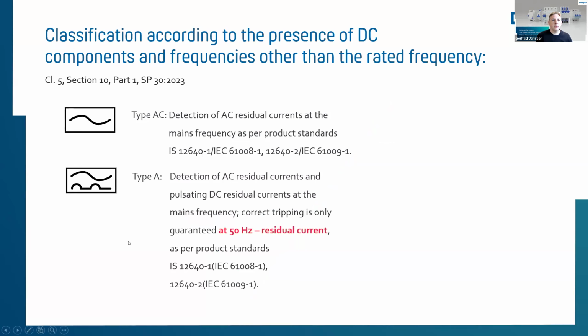When we come to the history of RCDs, everything corresponds to the presence of DC components in the different systems. So the classification is according to the presence of DC components and frequencies other than the rated frequency. We are starting with an RCD type AC, which is the most common one, still, I would say, in all of the world. I think as well in India, but as well in Europe and in parts of Australia. So AC is the main product still being used. It's capable of the detection of AC residual currents at main frequency 50 cycles, for example. This is stated in the Indian standards, but as well in the IEC standards.